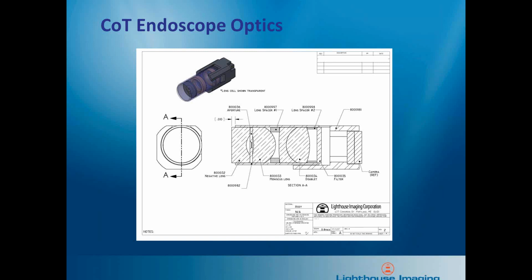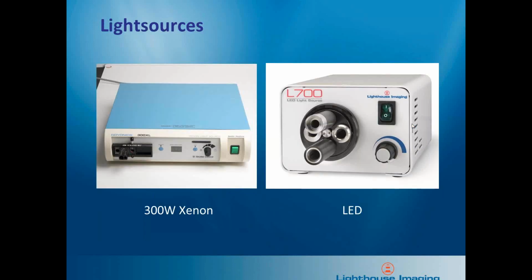So when it comes to testing the optics of flexible scopes, they typically are kind of more either good or bad. But the purpose of the Lighthouse tools in those cases is to make sure that the quality of the components that go back into them is equal or better than the OEM. So that's some background on the endoscopes themselves. Again, we also test light sources and light cables.